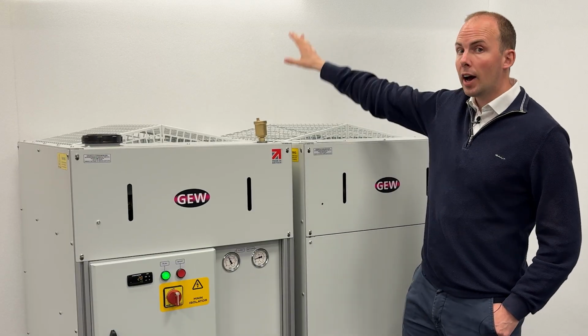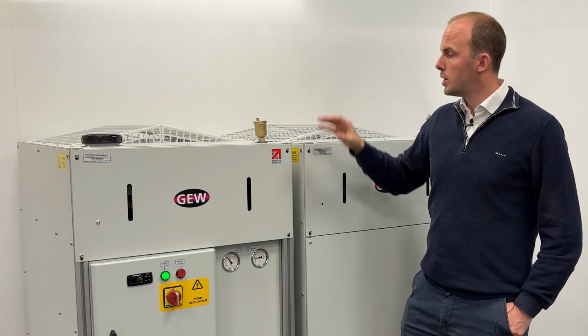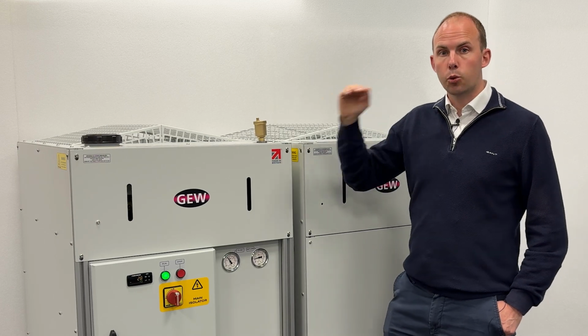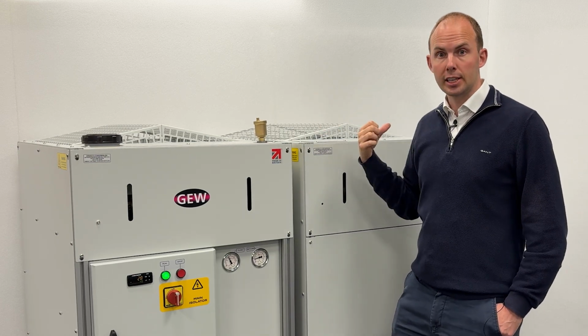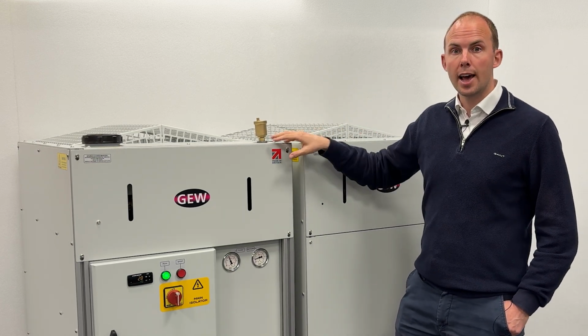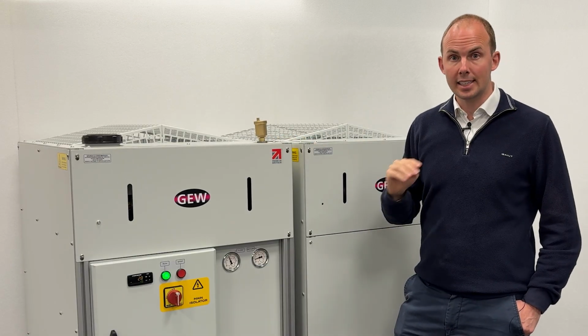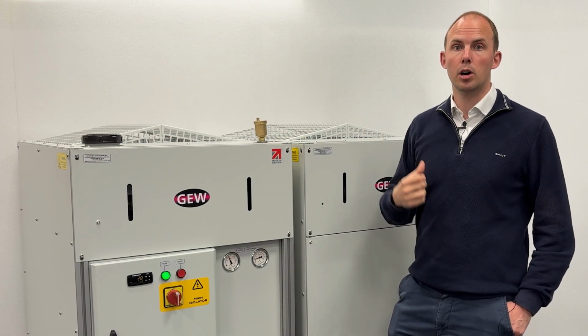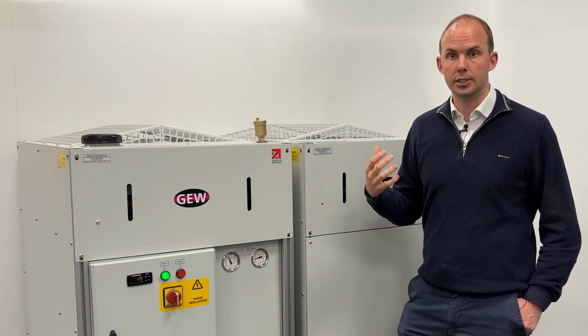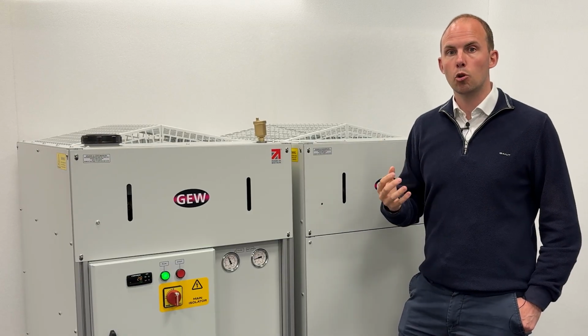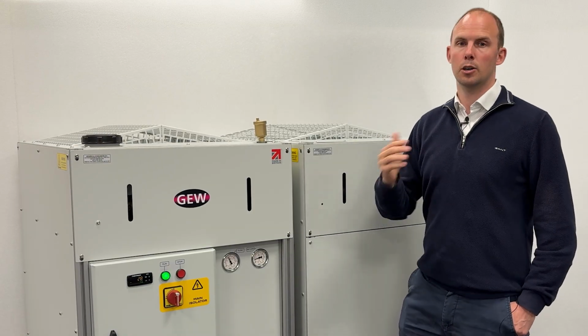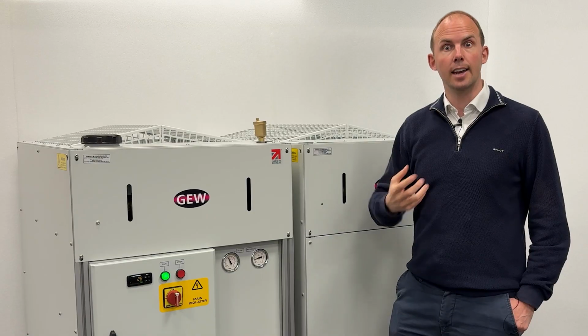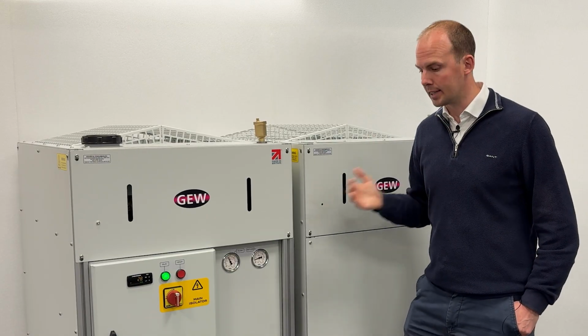Behind the unit on the wall, a chiller requires 23 kVA for a 32 kilowatt unit. The equivalent Air Blast cooler only requires 6 kVA installed power on your wall, your amps and your breakers. This means the installed power requirement is a quarter of what it is for a chiller, which is a big saving when installing this equipment.